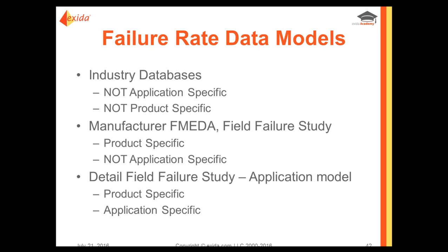So you can look at different failure rate data and failure rate data models. There are predictive and estimated failure rate data models, and on those, we have webinars. I actually did one last week on just the failure rate data models. But there are different ways to receive data for your calculations. There are industry databases, there's manufacturers information such as a FMEDA or a field failure study, and there's detailed field failure studies per application and models. And there are positives and negatives for every different failure rate data model, just like everything in life. Some are product specific, not application specific. Some are neither, some are both. So when you're looking at failure rate data, you need to see what the source is to see how applicable it is for your situation.